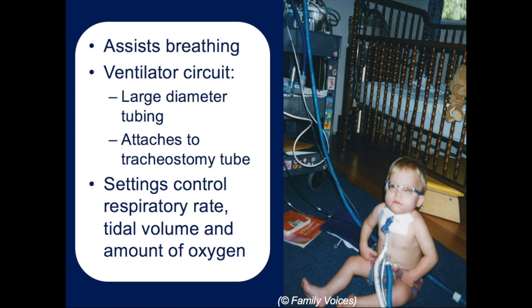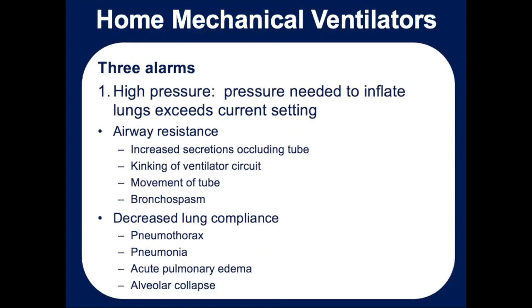Sometimes the complaint is, our ventilator, an alarm is going off, we don't know what's going on. A lot of times the alarms are triggered because the patient is having some type of event that is essentially alarming the machine, saying something is not right with the pressure, something's not right with the tidal volume, or something is wrong with the oxygenation. There are 3 main alarms that you might encounter on a ventilator. This is by no means meant to be a comprehensive lesson on how to troubleshoot or set up a ventilator. But understanding these basic concepts, you'll understand what it means if you see something that says high pressure or low pressure or low FiO2.